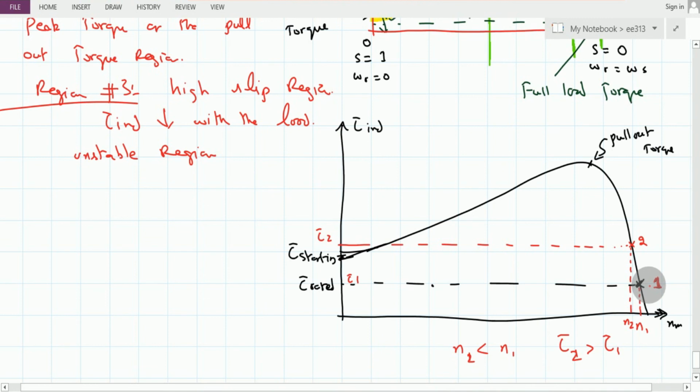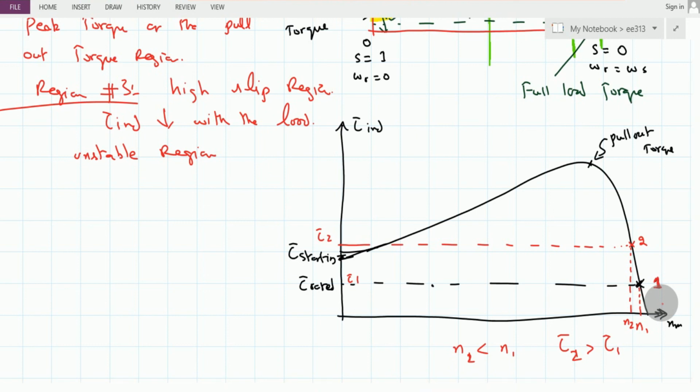And therefore this is a region where the motor torque and the speed complement each other such that the motor comes back to the original point even if there is some disturbance in its performance. This region is known as the stable region of the motor. So this stable region we have starting from this particular point, all of this is set as the stable region of a given induction motor.